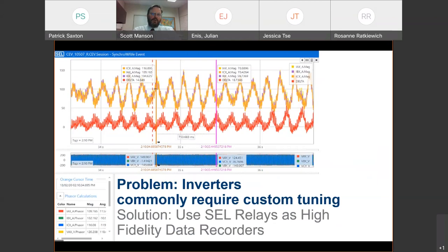Again, how do you know every time there's a firmware upgrade that it even works like you asked for it or you paid for it to work? You don't know unless you have a relay right there to tell you. Here's an example. We caught this very event with a relay. Here you can see an inverter oscillating unacceptably after a firmware upgrade. Not all upgrades are forward progress. And so we use the high fidelity, high speed sampling of the distributed intelligence of multifunction relays to catch the problems, to enforce consistency.